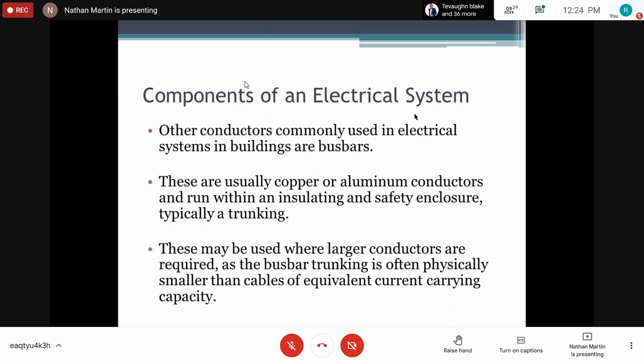Now, other conductors commonly used in buildings are bus bar conductors. So we're talking about the bare bus bar in an enclosure, right? It can be of the riser main type, or it can be your regular distribution box, right? But in fact, these are also conductors. Remember, we told you that the conductor is what carries the current. So the conductor can be a bar as well as a cable, right? These are usually copper or aluminum type bus bars, and are actually tucked away in an enclosure, typically a trunking type enclosure or a metal clad enclosure, right? Metal clad meaning the galvanized boxes that are colored gray. Most of them come in gray for installation purposes, right?